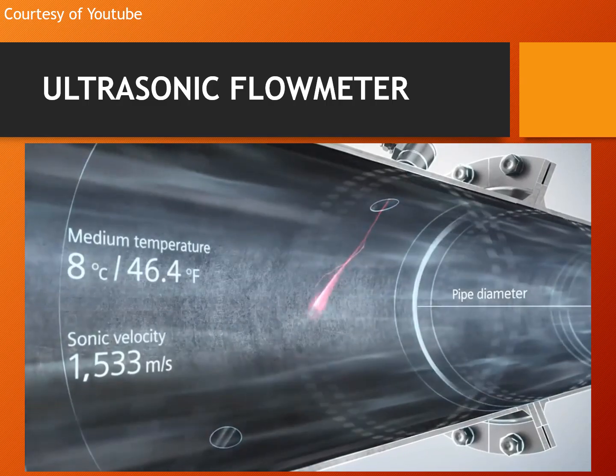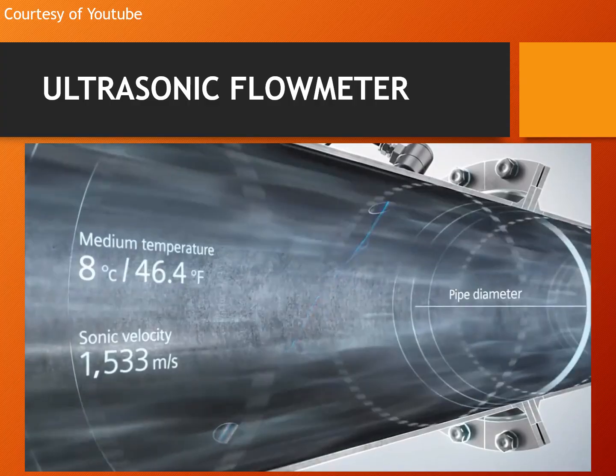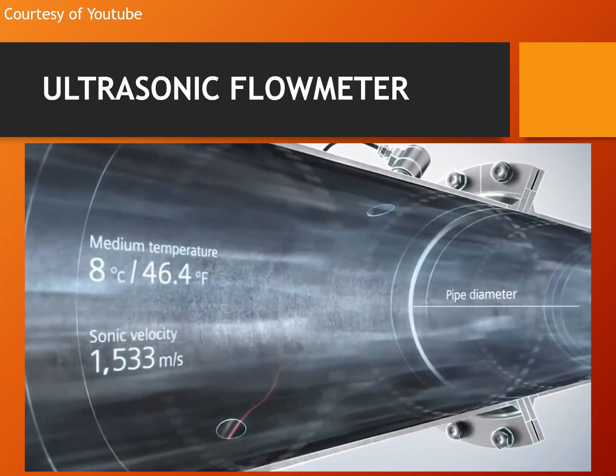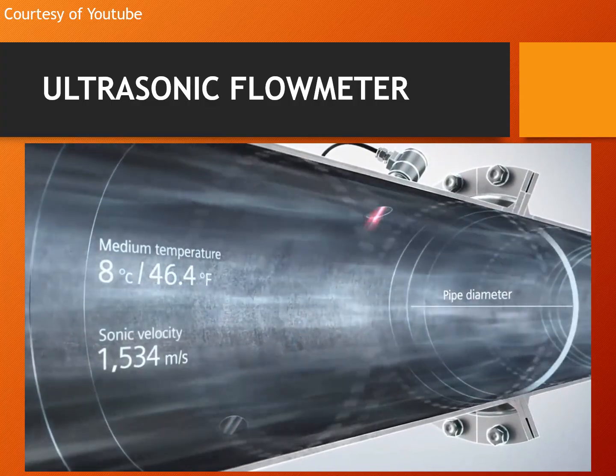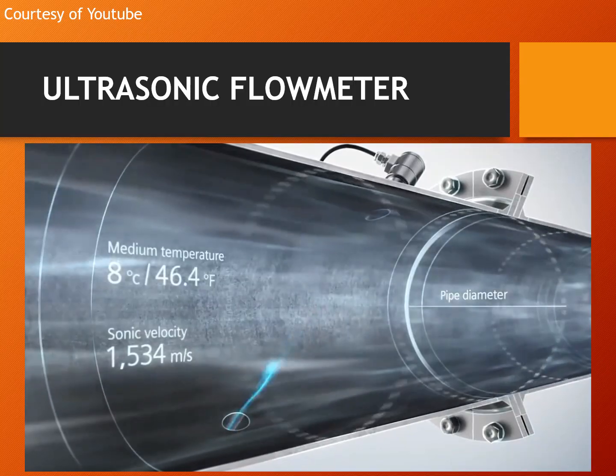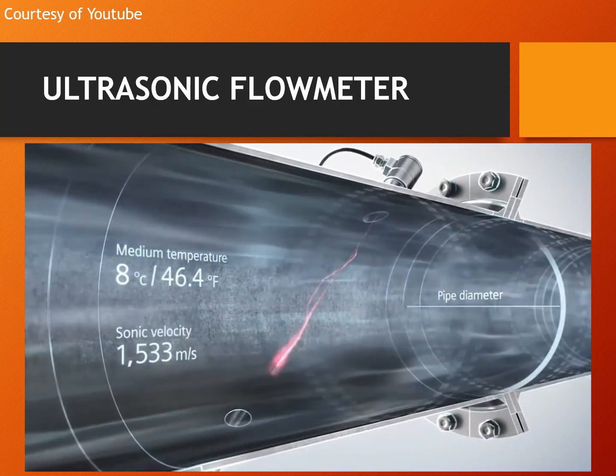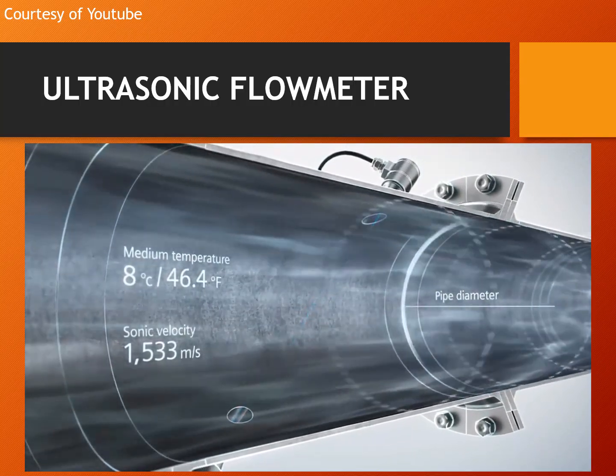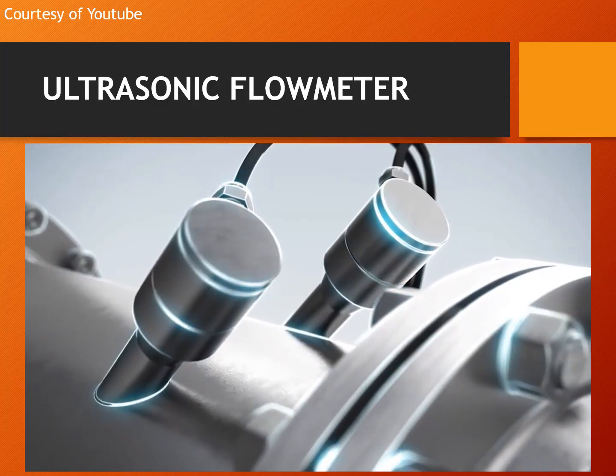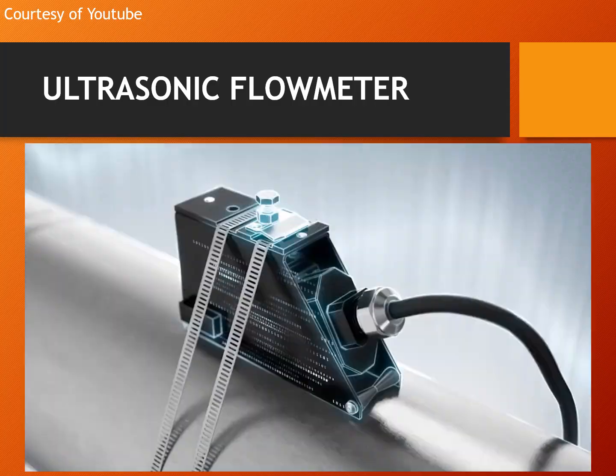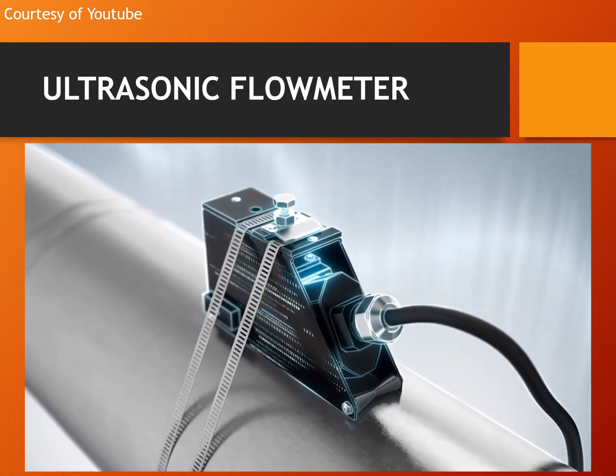Combined with the known area inside the pipe and the measured sonic velocity and temperature of the media, it is possible to accurately measure the volume and also to derive parameters like density and viscosity. As the flow meters have no parts that wear, measurements remain constant and the total cost of ownership low.